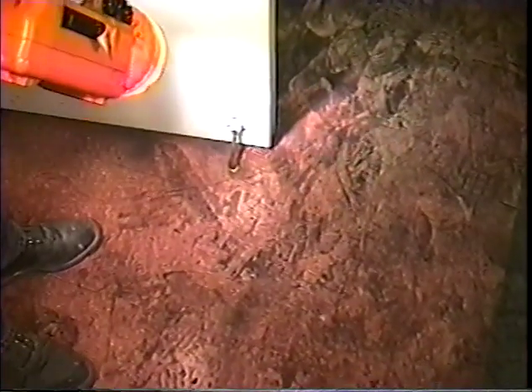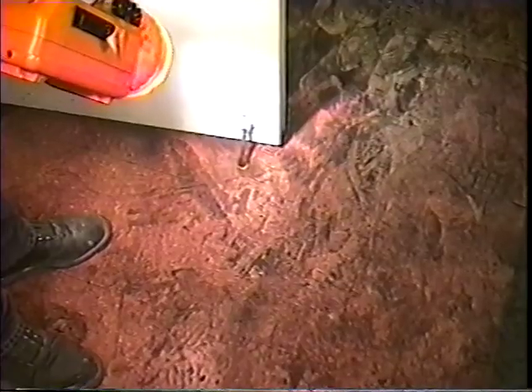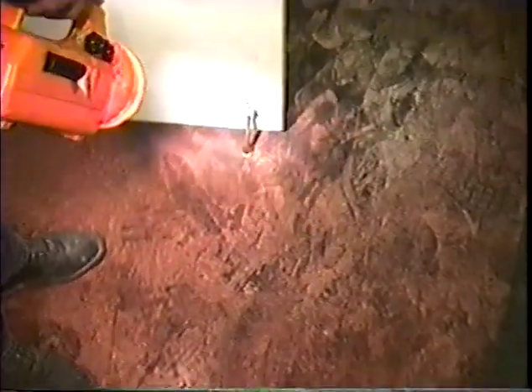You'll see once again several doors which are on self-closing devices and rated assemblies which were propped open during the time of the fire. This particular door, there's a pattern in the smoke showing where this particular drop arm may have been located at the time of the fire. Staining to the door, smoke on the interior threshold into what looks like a dressing room.